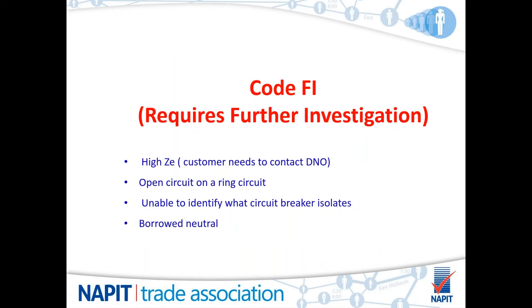The new amendment of BS7671 introduced code FI, further investigation. That doesn't mean to say that there are any new faults that have been unearthed that have never been coded before. It's just that this may need a little bit more investigation as to finding out why. A high ZE, when testing your ZE at the property, there could be a problem with the incoming supply, and therefore further investigation needs to be brought to the customer's attention so they can contact the DNO to investigate it.